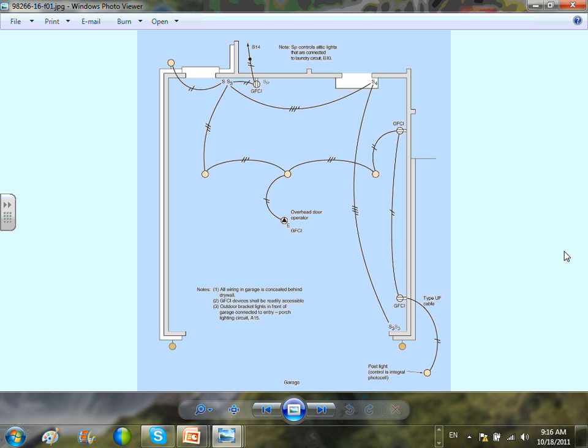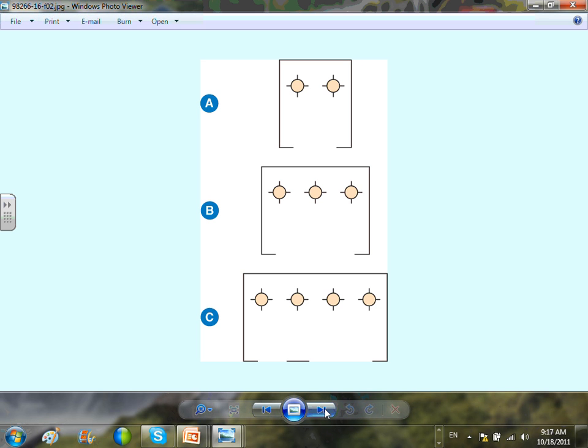If you have three-way switches, you need two travelers and a neutral and either a hot or a direct hot. So you need 4 conductors. You're looking at 4 conductors. So keep this in mind as you go through wiring these.